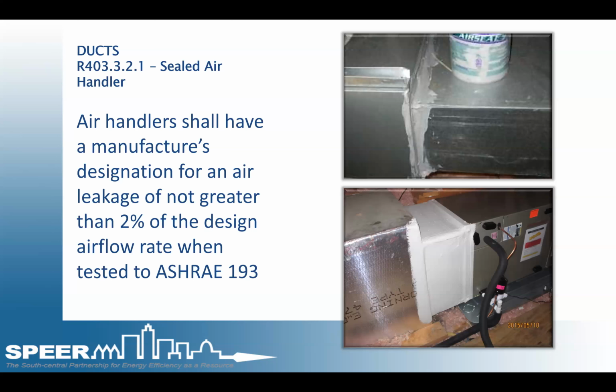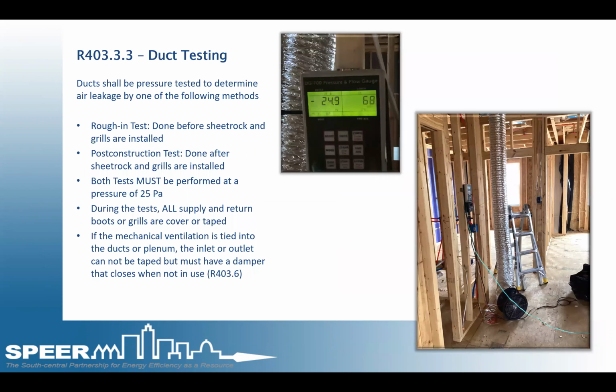So even though these have rubber grommets that come from the manufacturer, these are easy areas that can be additionally sealed to lower cabinet leakage and allow for more leakage to happen in the duct test, in the duct system. So that is easier for the contractors to get a passing score on a duct test.